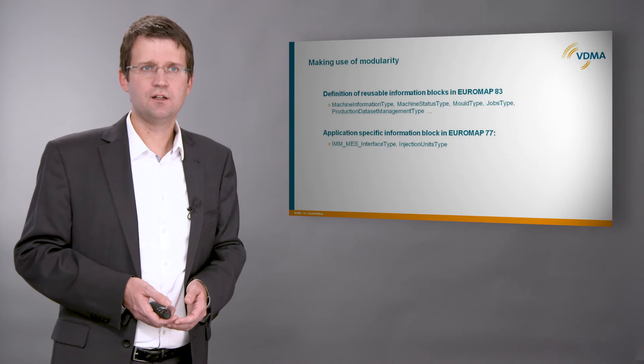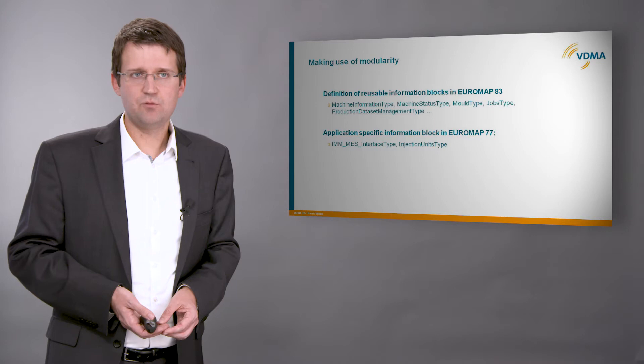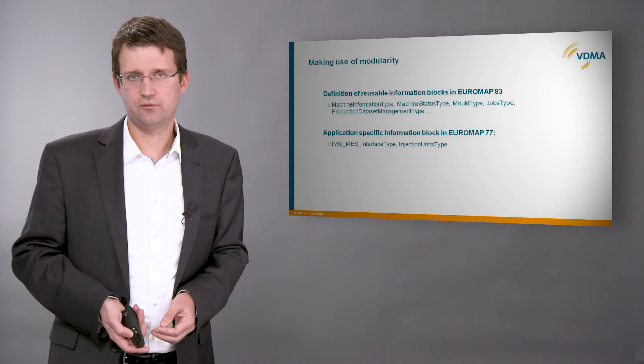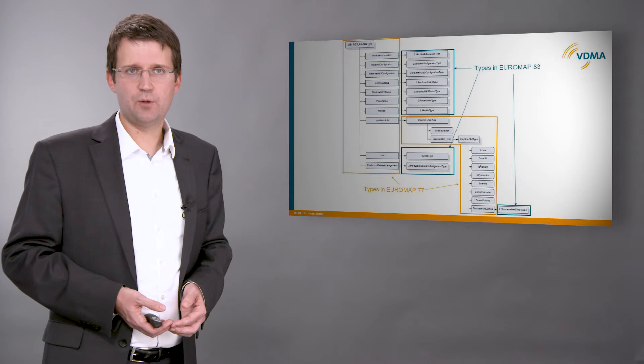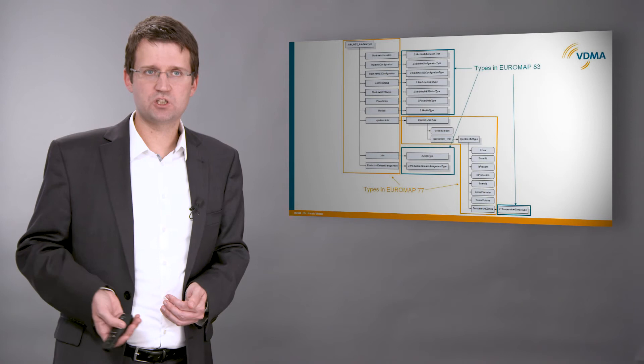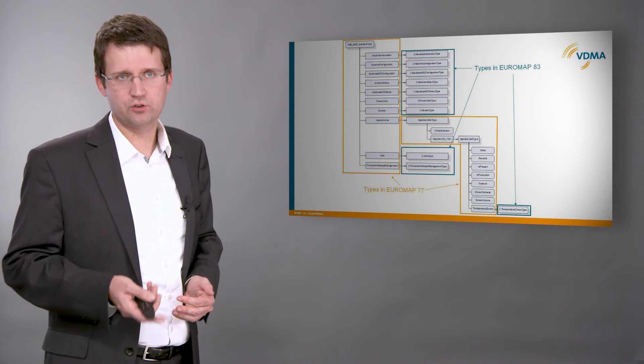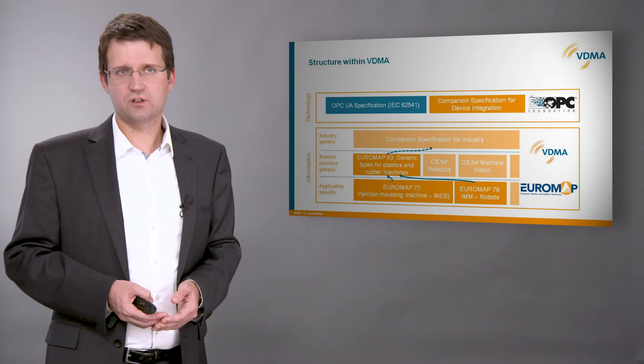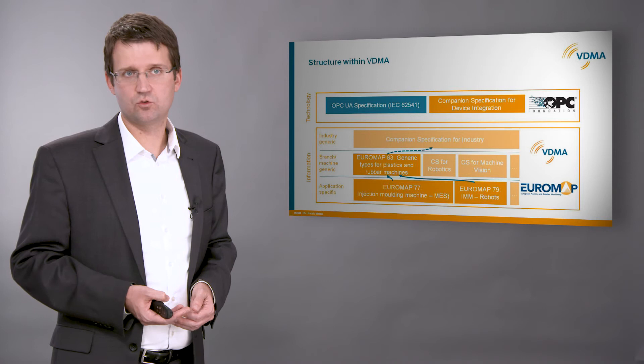As Euromap 77 is not the only specification for plastics and rubber machinery, a common structure became necessary. For this purpose, Euromap 83 was created. This includes requirements and type definitions that can be reused in the application-specific information models for different use cases. When looking at Euromap 77, most of the use types are now defined in Euromap 83. The definition of job and dataset management had been defined in a general way, so that it can be used for injection molding machines, but also for blow molding machines, extruders, or other machines. A special type definition in Euromap 77 then includes an injection unit type, because this is only relevant for injection molding machines. Within this type, all the components defined in Euromap 83 can be used, which is done here with the temperature zone type.